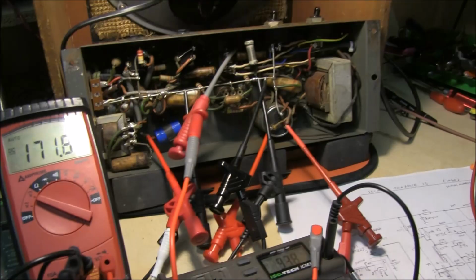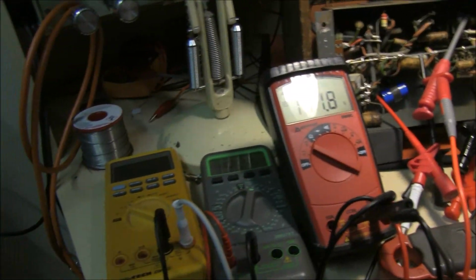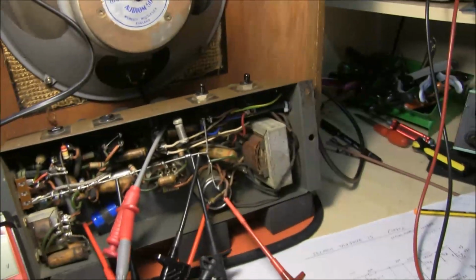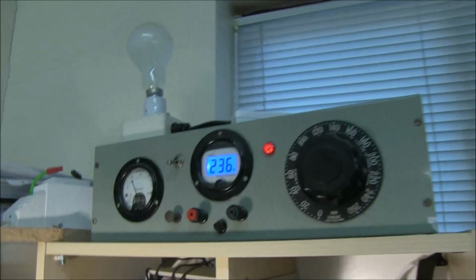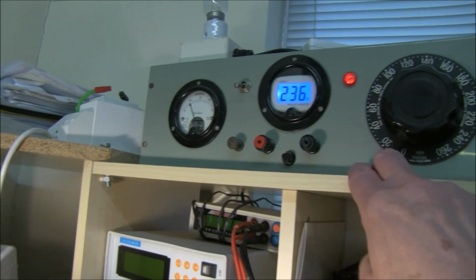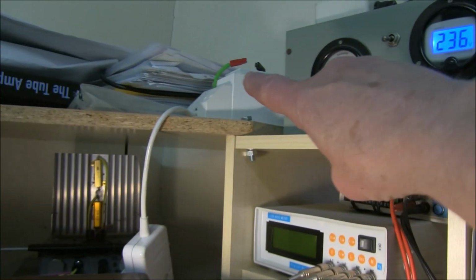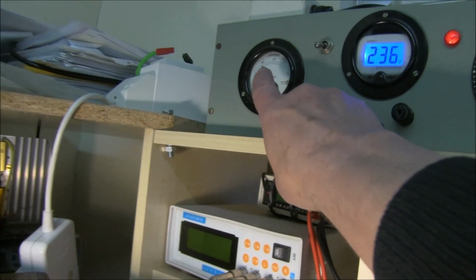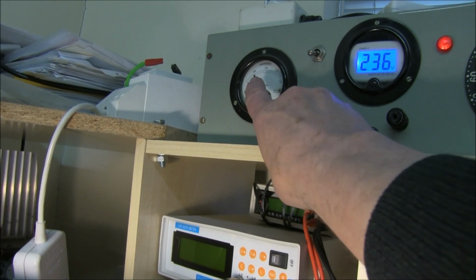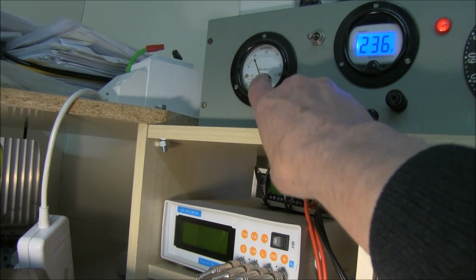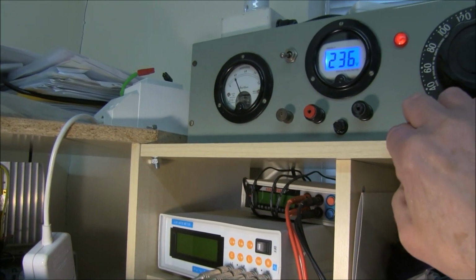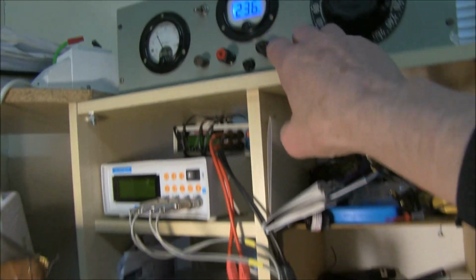So I've connected up below the voltage monitors to the circuit, and I've slowly ramped up the voltage on the Variac through the isolating transformer, drawing just below about 400 milliamps. I assume that's mainly due to the heaters, 236 volts. The voltage is a bit low.